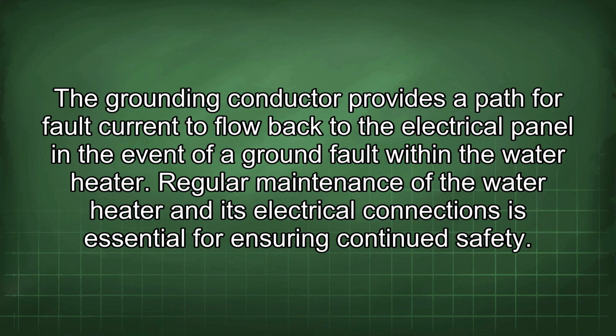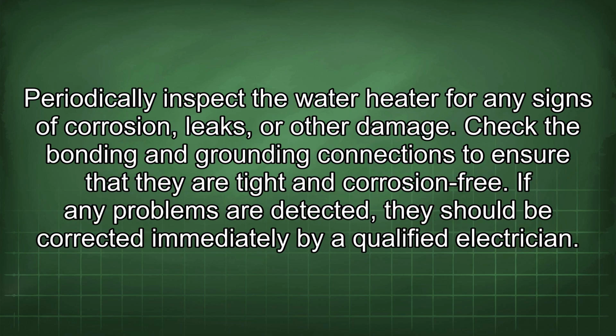Regular maintenance of the water heater and its electrical connections is essential for ensuring continued safety. Periodically inspect the water heater for any signs of corrosion, leaks, or other damage. Check the bonding and grounding connections to ensure that they are tight and corrosion-free. If any problems are detected, they should be corrected immediately by a qualified electrician.